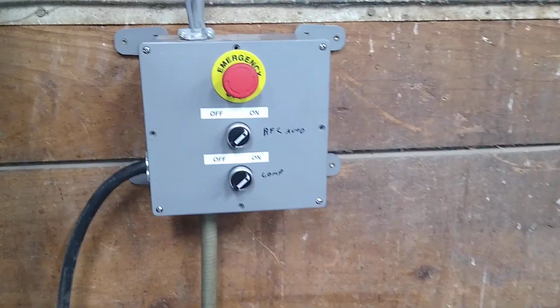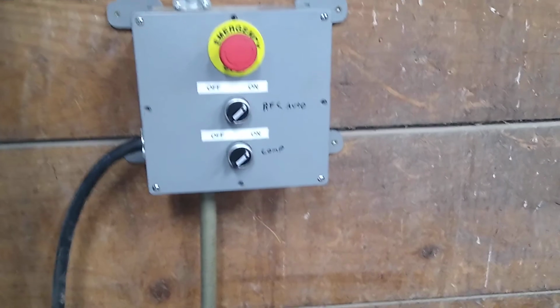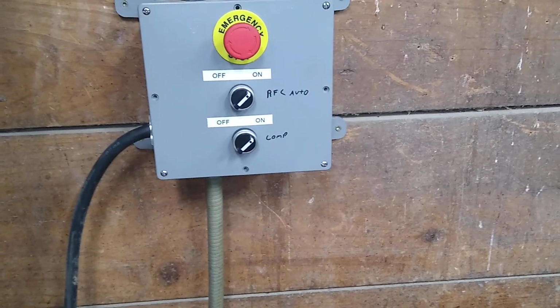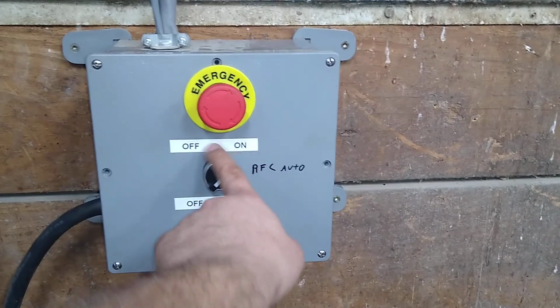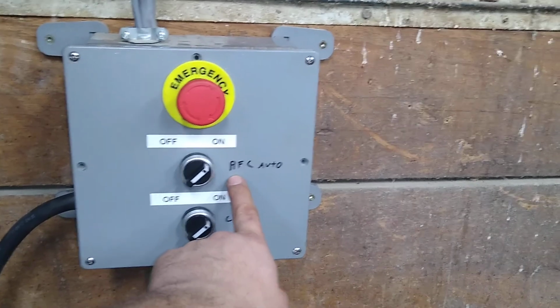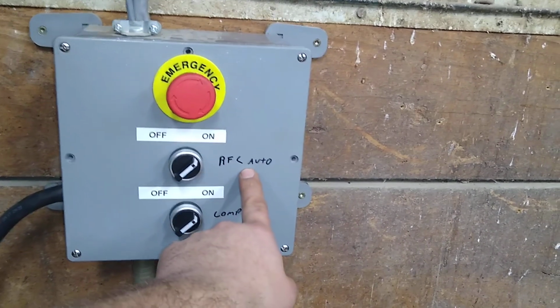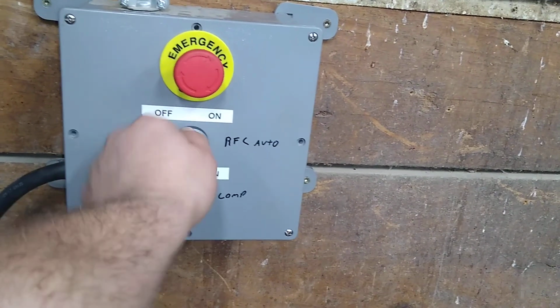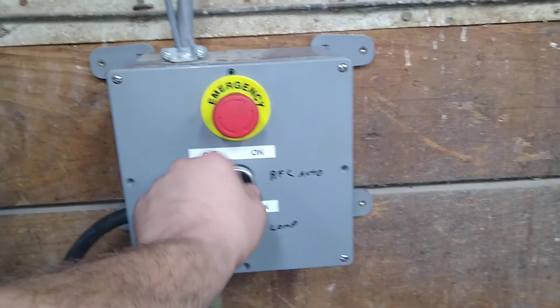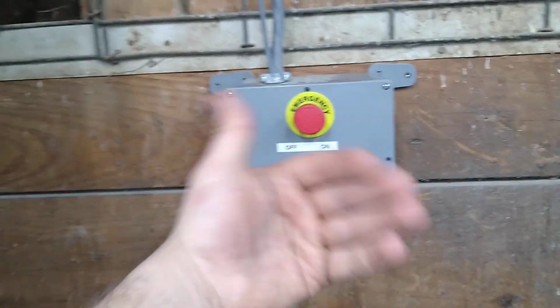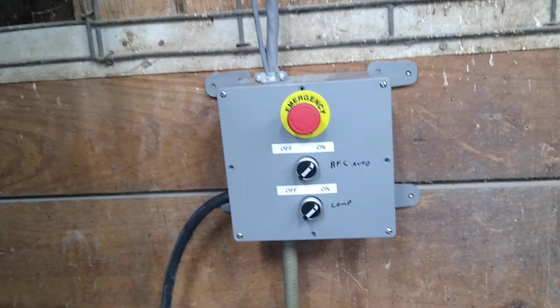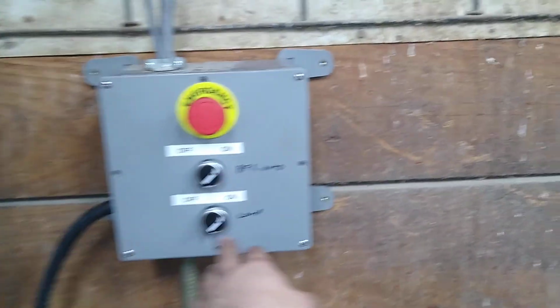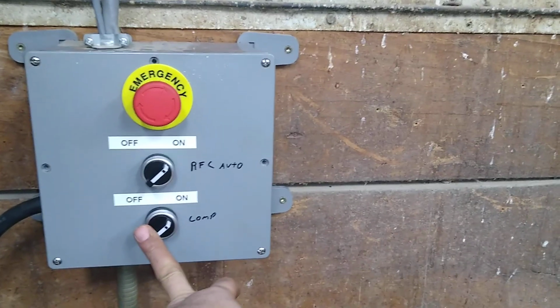But this one, I can't turn on the rotary phase converter just by itself, because as you can see, it's on. But I need to get another label to cover this up—it's a rotary phase converter auto switch. So if I turn this off and the compressor calls for air, it's not going to turn on. When I turn this on, the compressor calls for air, the rotary phase converter will start up and do that. And then there's just the compressor on and off in general.